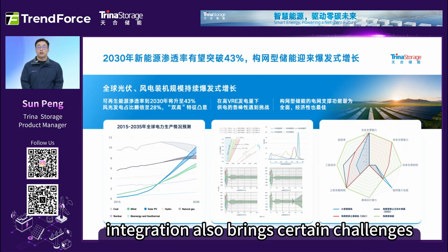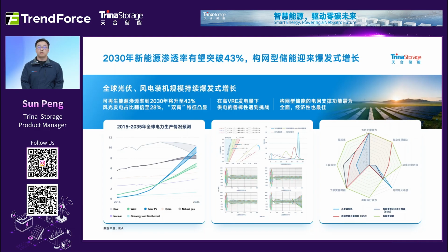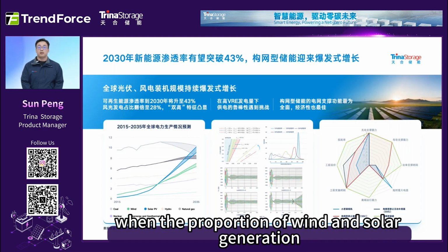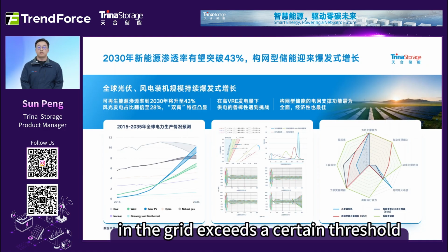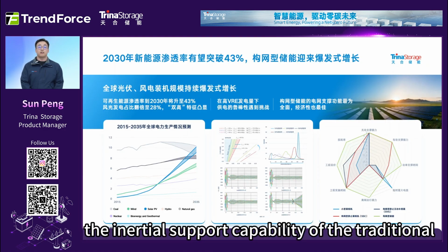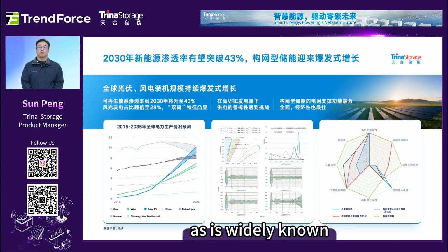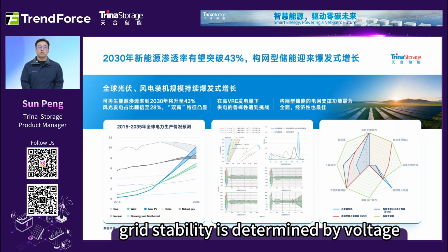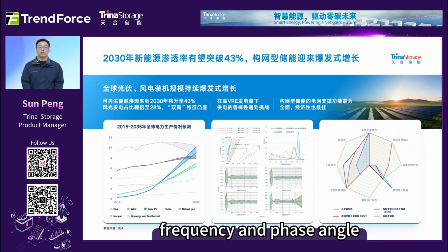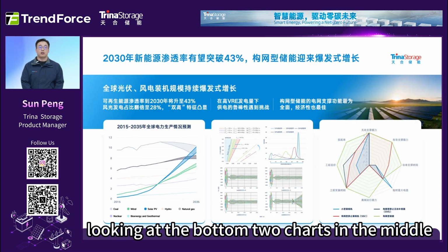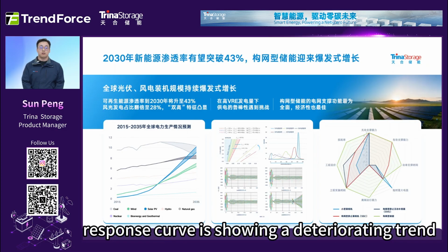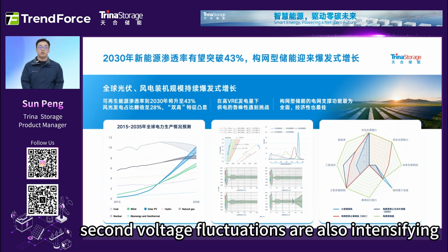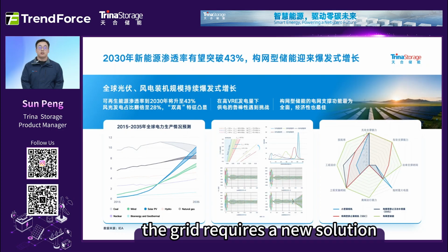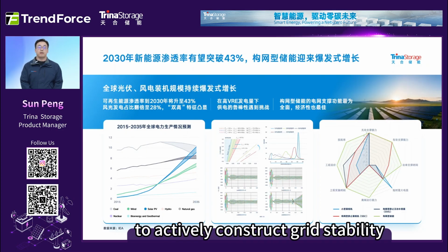However, this massive integration also brings certain challenges. As shown in the middle charts, when the proportion of wind and solar generation in the grid exceeds a certain threshold, the inertial support capability of the traditional grid drops sharply. As is widely known, grid stability is determined by voltage, frequency, and phase angle. Looking at the bottom two charts in the middle, first, the frequency response curve is showing a deteriorating trend. Second, voltage fluctuations are also intensifying. At this stage, the grid requires a new solution to actively construct grid stability.